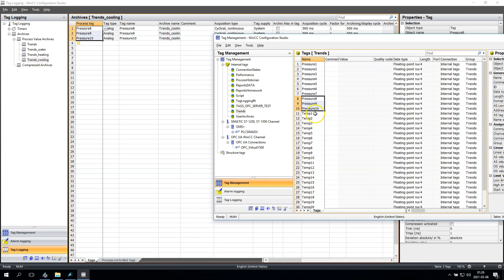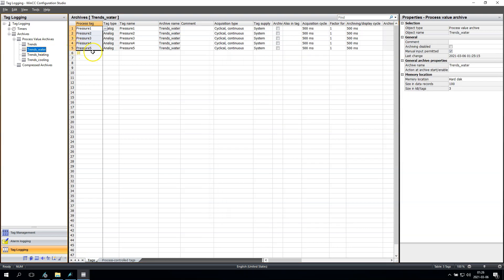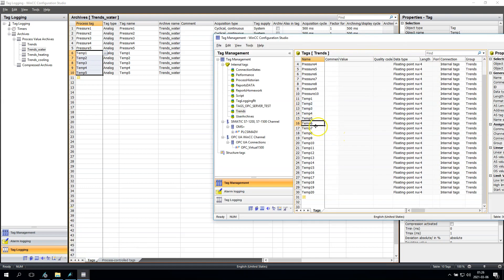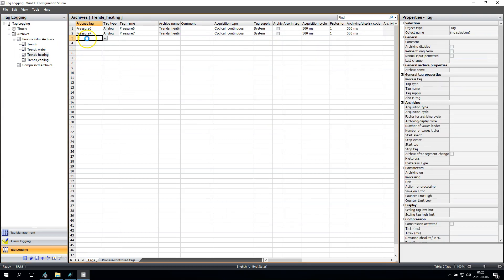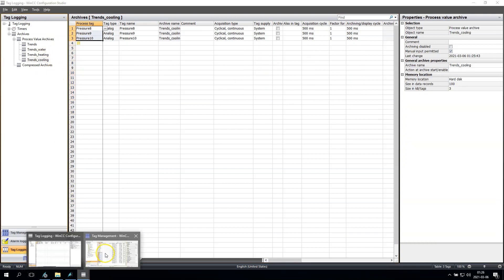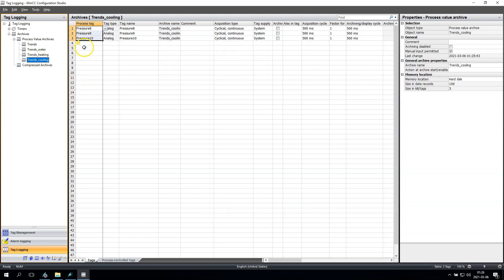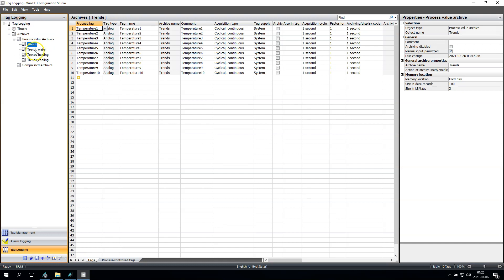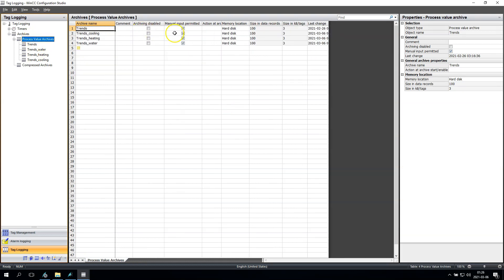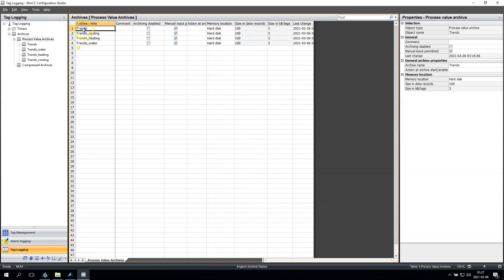I have five pressures in water, two pressures in heating, and three pressures in cooling. The same we will make for temperatures: water temperatures — five; temperatures for the heating system — usually heating has more temperatures; and for the cooling system only two temperatures. So we now have the process value archives and tag logging configured in our system. After we run the WinCC runtime we will see that these internal tags are logging into the system and we can display this data on our WinCC Online Trend Control.